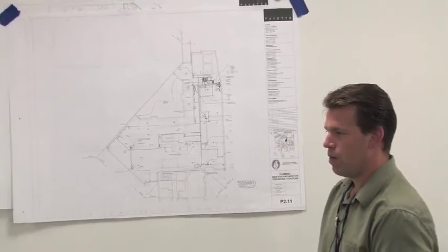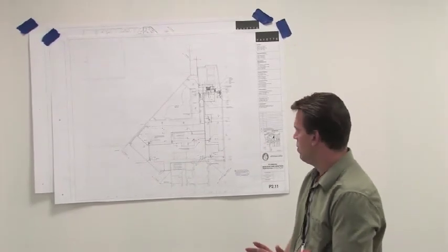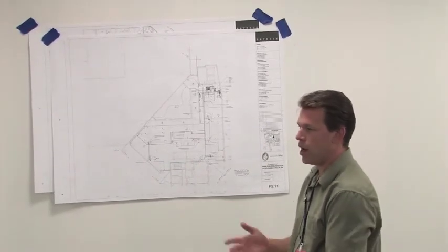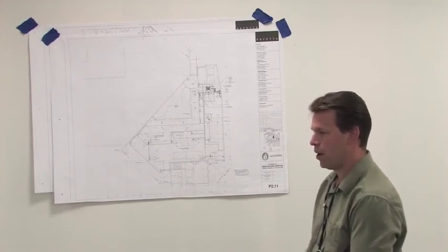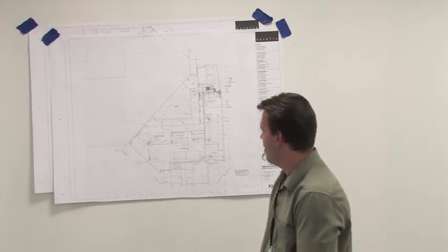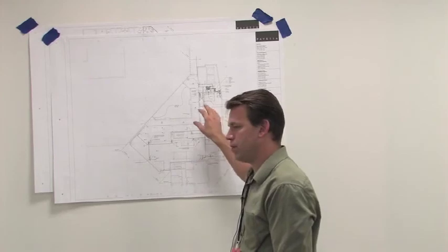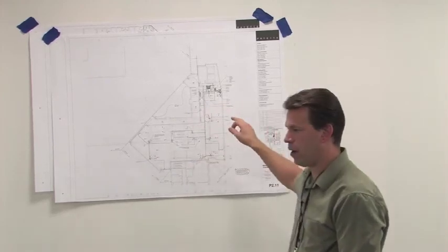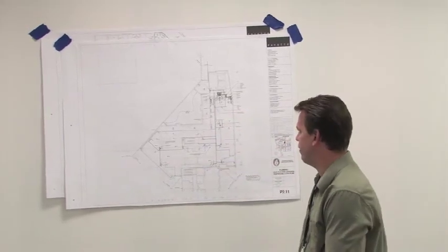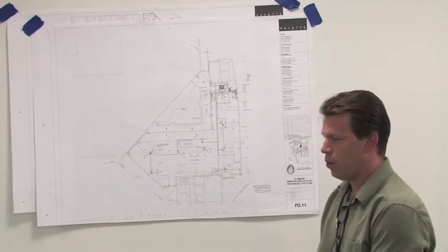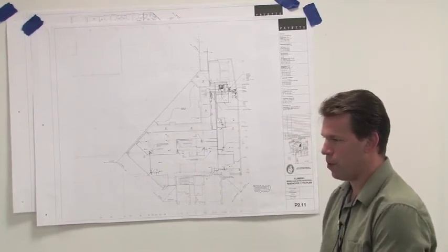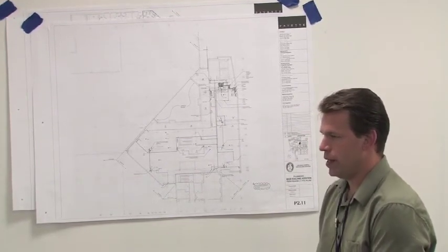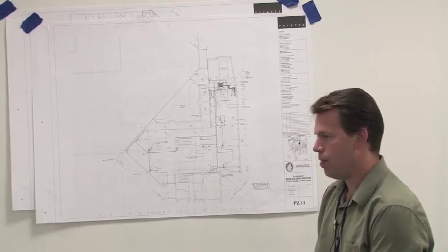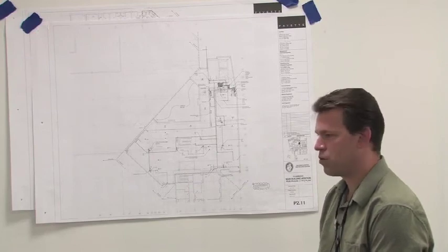Well, it'll be always on. If it needs water, it'll come through that pump. We're really right on the edge as far as water pressure goes getting to that cooling tower. I believe Eric needed 50 psi there, and we're very close. After the backflow, I think we'll be below that. What enables that pump, from a control standpoint? You've got to remember the cooling tower will only be operable for about 4 months out of the year.